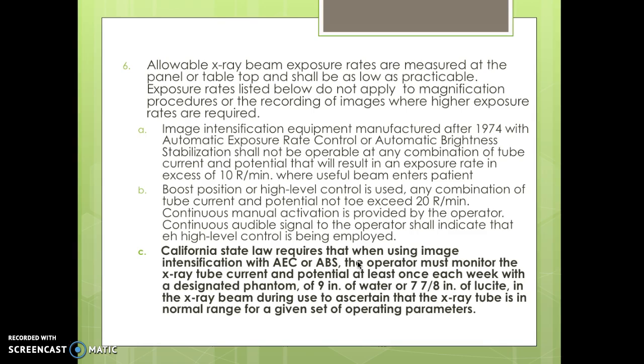Allowable x-ray beam exposure rates are measured at the panel or tabletop and shall be as low as practical. These exposure rates do not apply to magnification procedures or recording of images where higher rates are required. Image intensification equipment manufactured after 1974 with AEC or ABS shall not be operated at any combination of tube current and potential that will result in an exposure rate in excess of 10 R per minute where the usable beam enters the patient.